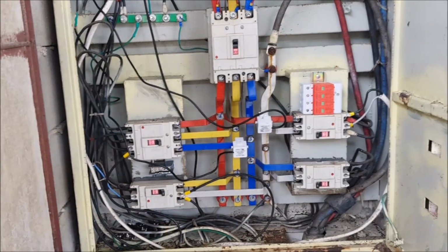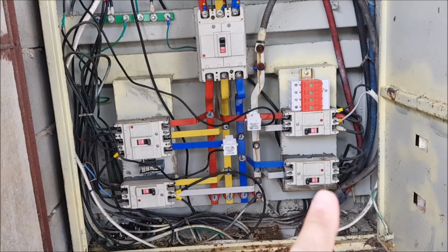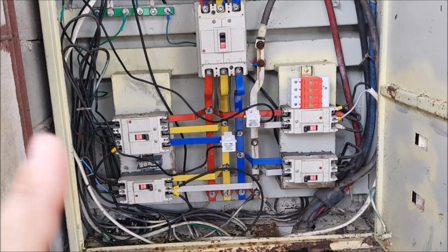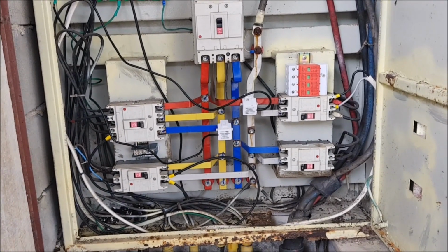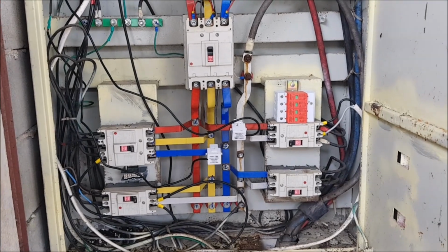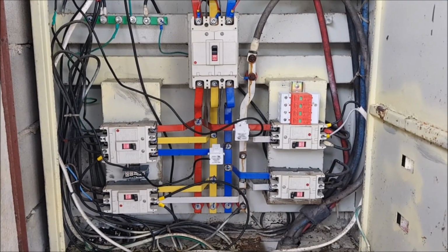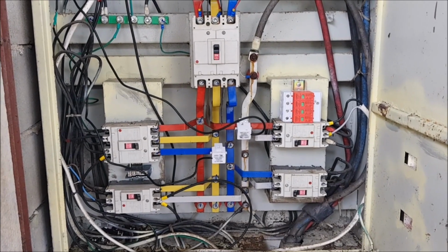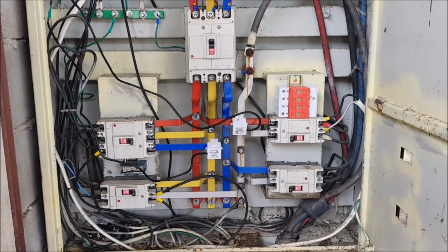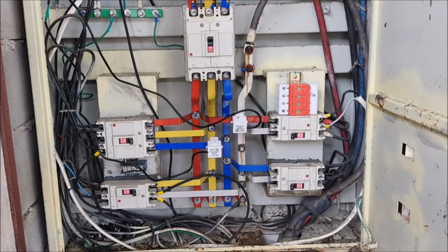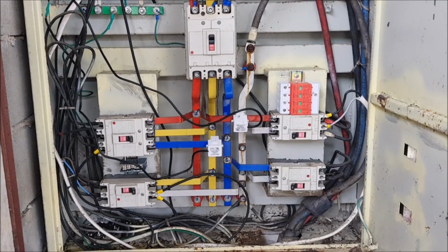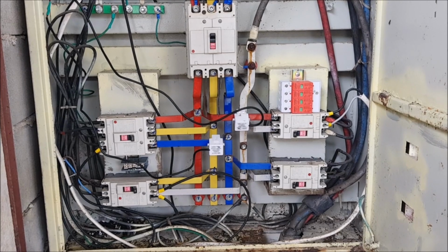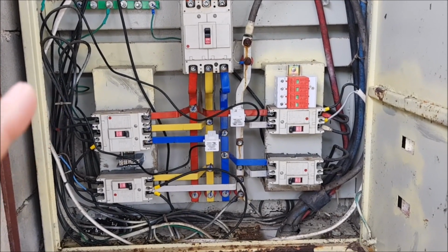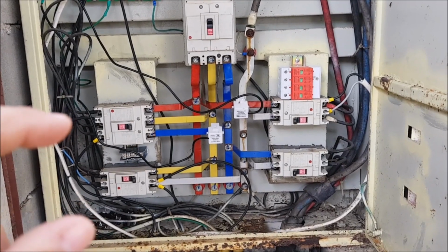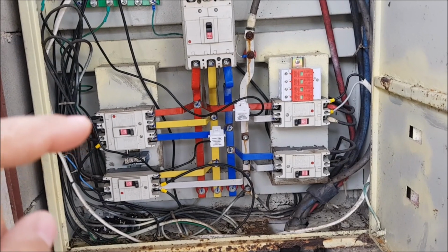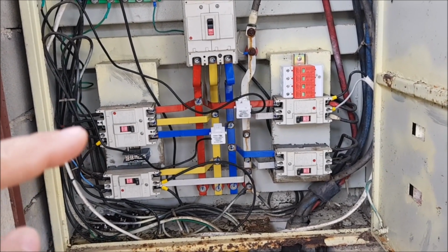These are all quite big bus bars, and they then go to other breakers, which then take cables to the next distribution points. So in the initial parts of the distribution, the only thing usually taken care of is short circuits. These massive breakers should never trip when something happens at the later parts, downstream, in your load centers, in your buildings, etc. These breakers should trip only when something happens like this one, which is our main breaker of interest today.